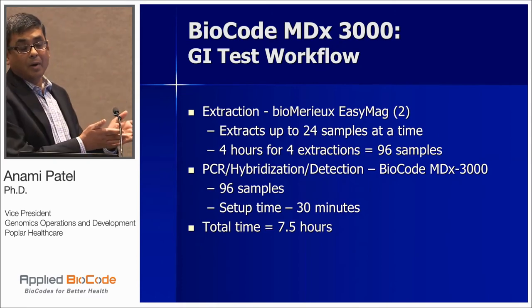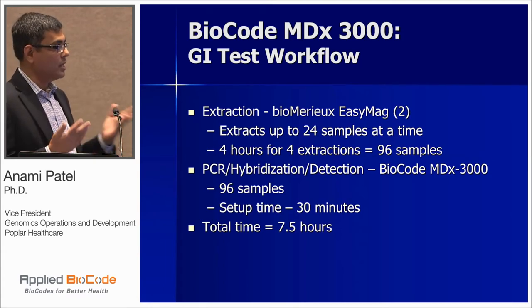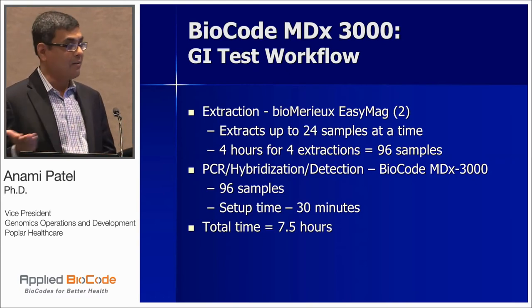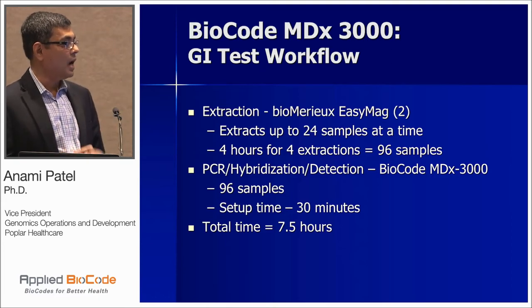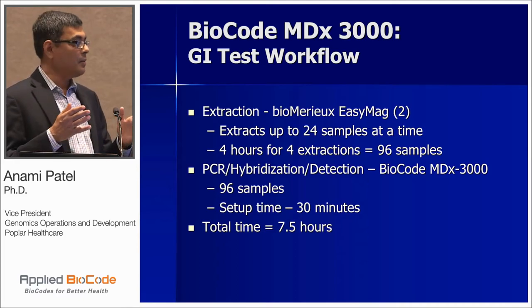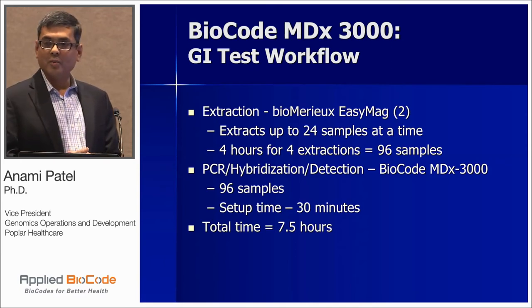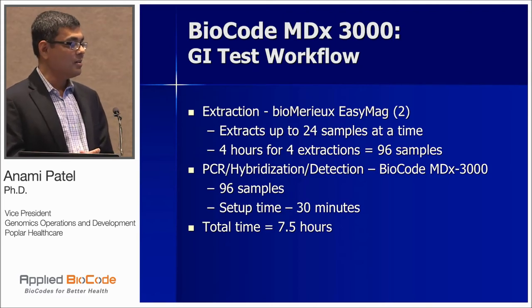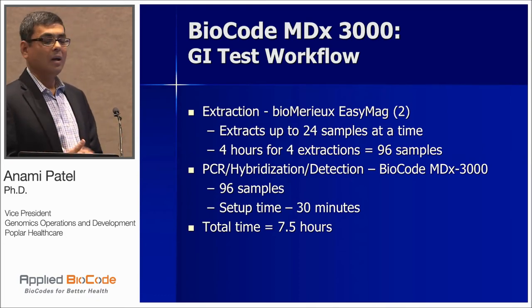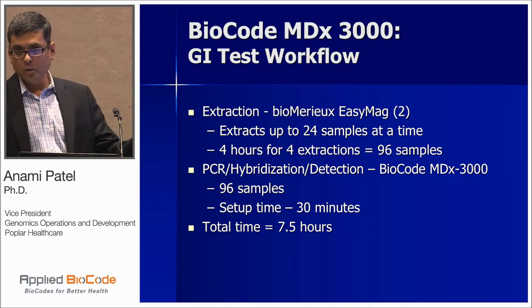Thinking about my current workflow with the Luminex system compared to the BioCode 3000 system: the GI workflow would still include extraction on my EasyMag — two EasyMags would take the same time period, so no advantage there. However, once I have extracted nucleic acid, I can straight go and put my nucleic acid on the 3000 system — up to 96 samples — and that setup takes about 30 minutes. Then I turn on the instrument, load the required reagents and consumables, and in about three and a half hours I get results for all 96 samples.